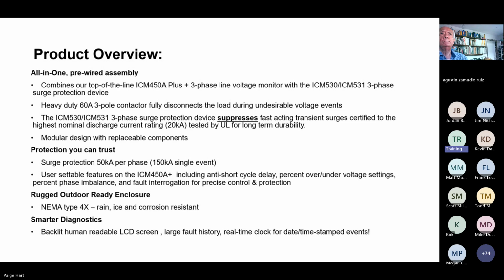This control also is housed in a rugged outdoor ready enclosure, a NEMA Type 4X enclosure, which is resistant to rain and ice and corrosion, and is great for outdoor applications, making it an easy device to just put outside next to the piece of equipment and wire right in. It's got smarter diagnostics, meaning that instead of just dummy lights or basic feedback, this has an actual human readable LCD screen that's backlit for low light conditions.